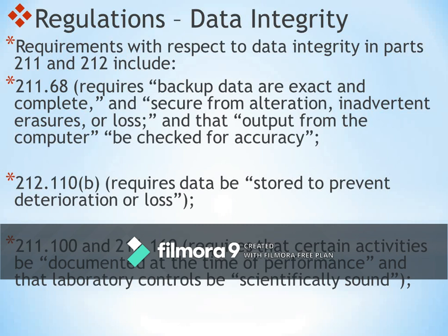It includes that 211.68 requires backup data are exact and complete and secure from alteration, inadvertent erasures or losses, and that output from the computer be checked for its accuracy. 212.110B requires that the data be stored to prevent its destruction or loss.